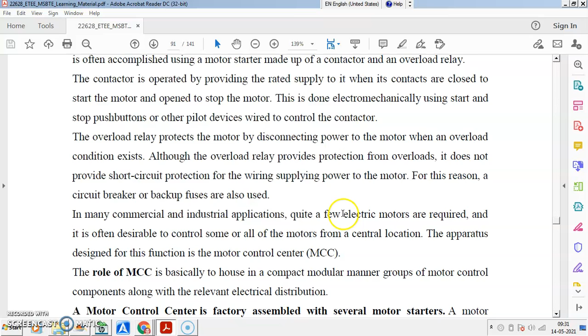Suppose I consider a single phase or three phase induction motor, every motor comes with a starter. Some motors require a direct online starter. Some motors require star delta starters, depending upon the starting current of the machine and the capacity or rating of the machine. So when a motor has more than 5 kilowatt rating, we go for a star delta starter. If the motor rating is less than 5 kilowatt, three phase, we go for the direct online starter. Some provisions we have made in the direct online starter.